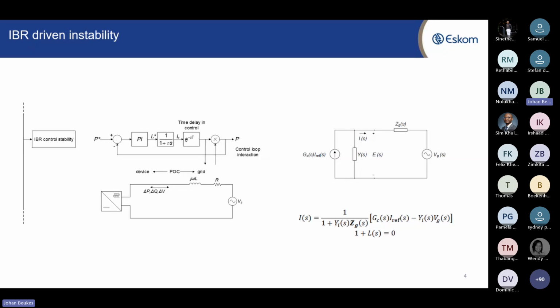It is purely related to the control system of IBR, and specifically grid following IBR. The two main aspects here are things that cause instability in the power control loop. So in a typical IBR control, you have a power control, and this is just a normal standard feedback control system. And you have a voltage control loop, and these two control loops can interact with one another.